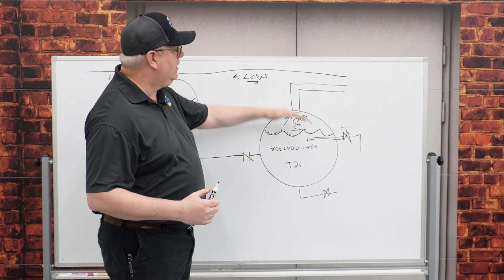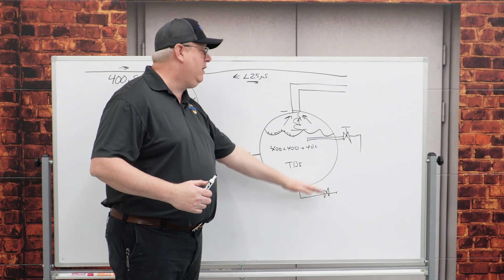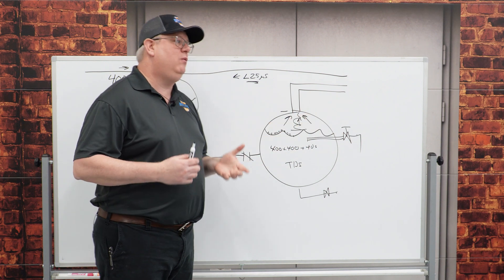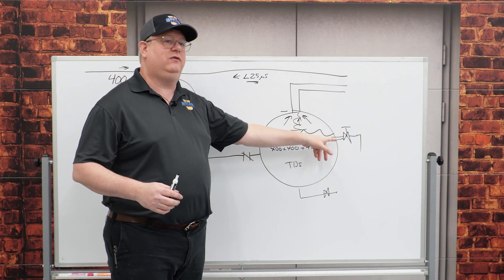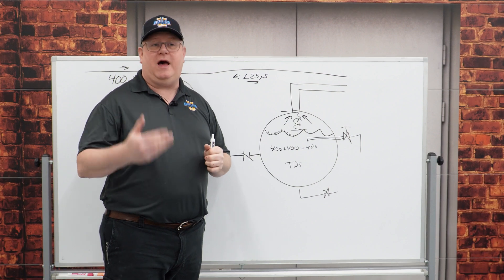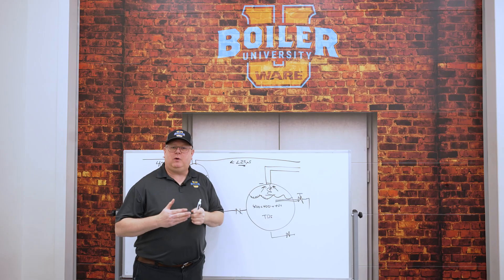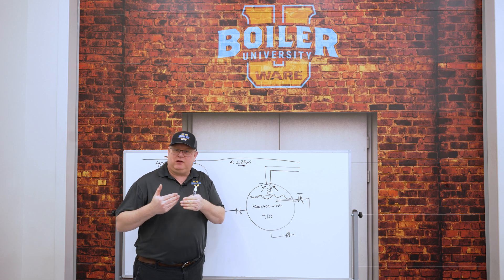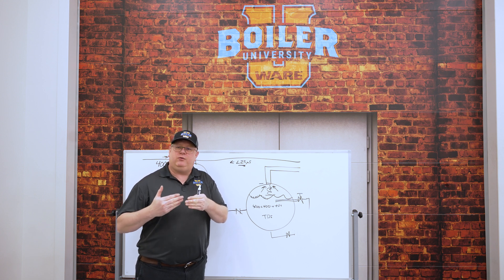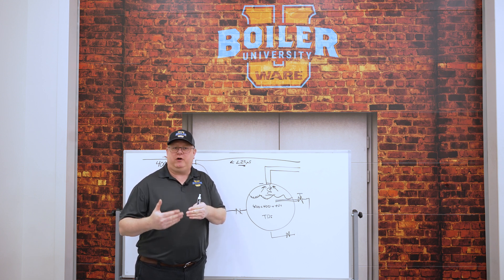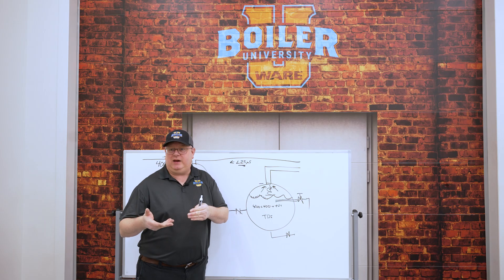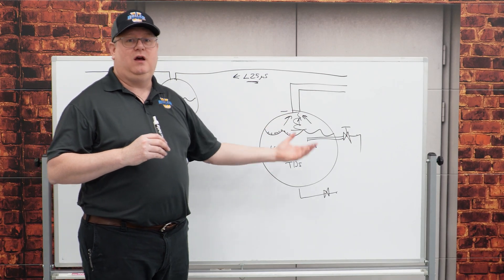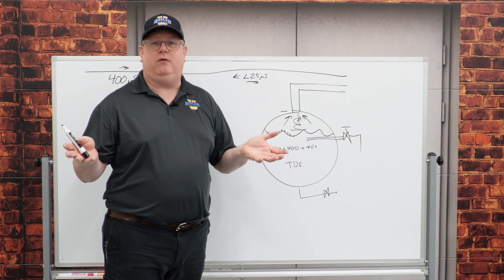With high conductivity and carryover, we can do some blowdowns, check for blockage on the skimmer line, and we may need to check calibrations if we have an automatic conductivity control. There's a probe in there measuring the resistance of the water, and if we get a deposit on that probe or it's fouled, it's not going to read accurately. My policy on high conductivity: if in doubt, blow it out.